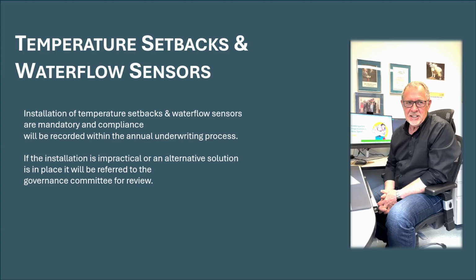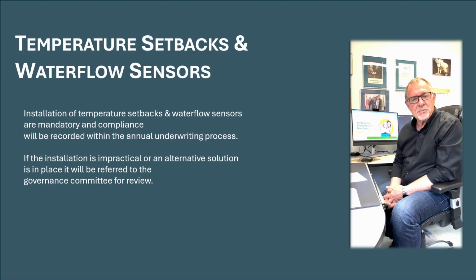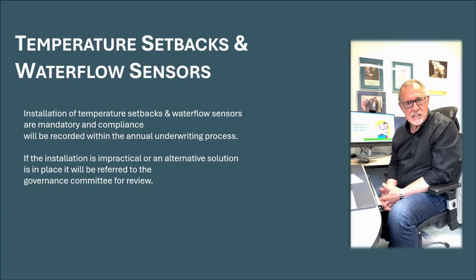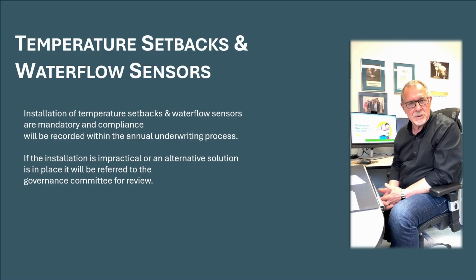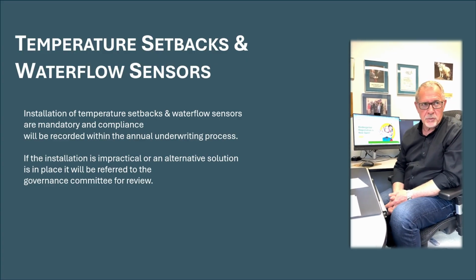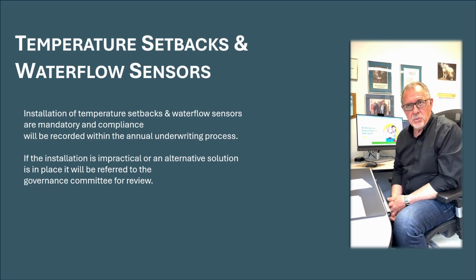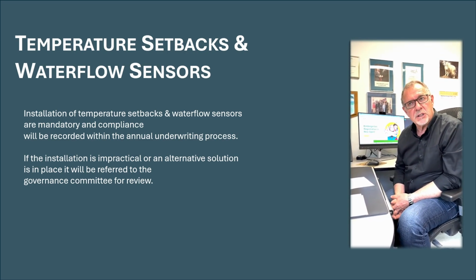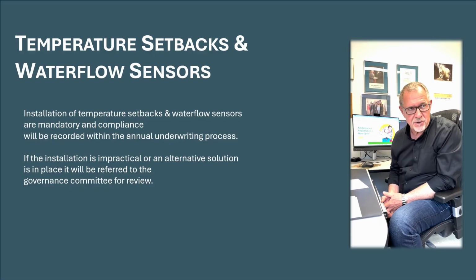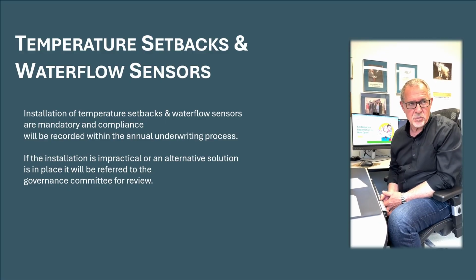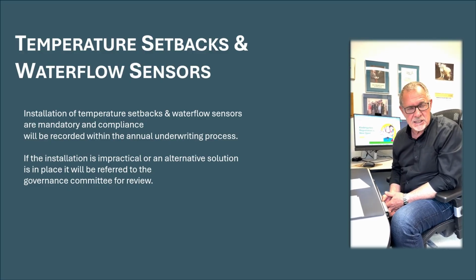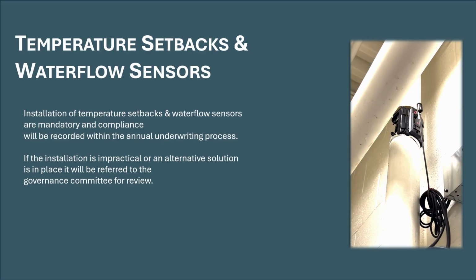Water flow sensors detect any anomalies in the water usage and flow and can automatically shut off the water supply, turning major losses into minor ones. Our school division. So sometimes to get to these emergencies or situations that need repair, it's not as quick as we'd like. So to alleviate that problem, we've come up with a system that will monitor how much water we're using. And if there's any deviation from this, any anomalies regarding how much water we're consuming, this system will shut the water off. So this is the heart of the system.